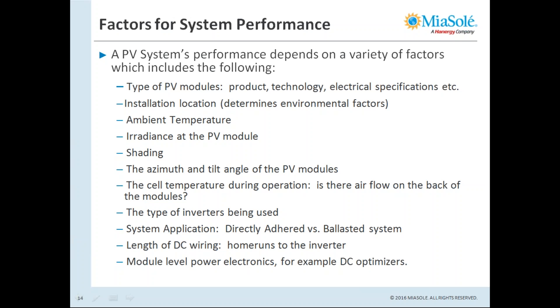Factors affecting system performance include: what type of modules you're using; where the system is located — is it hot and bright or cold and cloudy; is there shading at the site; the tilt and azimuth of the system design; how hot the cells get, since hotter cells produce lower voltage; inverter efficiency; airflow on the back of the panels; ohmic losses over home run cables back to the inverters; and whether there are module-level power electronics like optimizers. Any quality issue in installation can also impact system performance. Even a system with higher DC capacity can easily produce less energy based on all these factors.